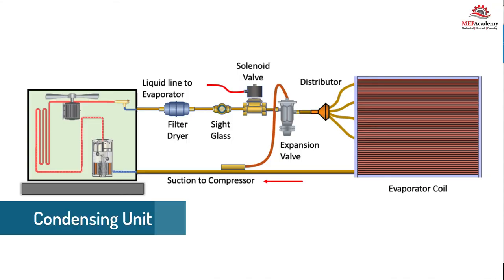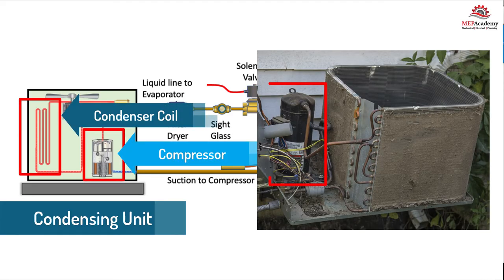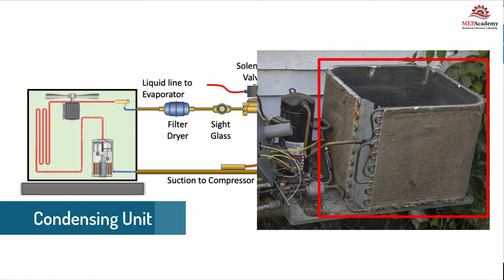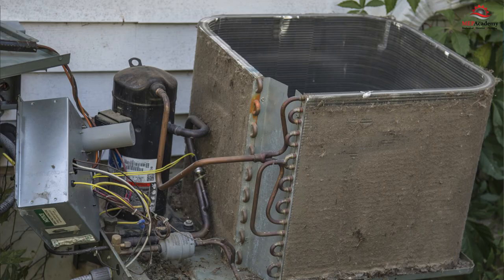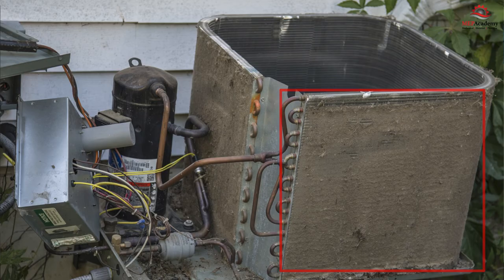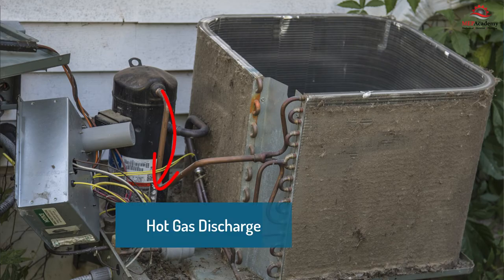The condensing unit contains two major components: the compressor and the condenser coil. The compressor is the heart of the unit and pumps the refrigerant around the piping circuit. The condenser coil provides a means of rejecting the heat to the outdoors using a fan blowing air over a hot coil. In this picture we can see that this condenser hasn't been maintained and is covered with dirt. This will reduce the capacity of the unit, so be sure to check your outdoor coil at least once or twice a year to ensure it's clean. We can see the hot gas discharge piping coming off the top of the compressor and feeding the condenser coil, which is responsible for rejecting the heat from the building.